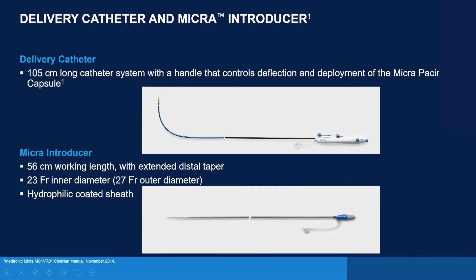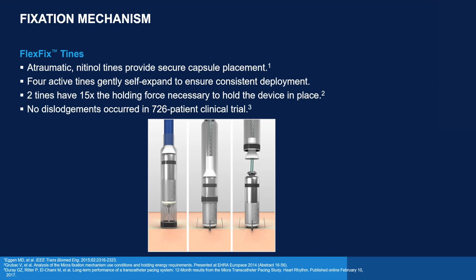So what happens when we unsheath the device is the tines open up. If you look here, the device is within the delivery catheter and the tines are folded up. As the delivery sheath is withdrawn, the tines open up and grip onto the trabeculation in the right ventricle. The apical section of the right ventricle is very trabeculated, with lots of crypts and crevices where these tines grip and basically hold the device in place. We also have the ability to test that it has actually gripped before we disconnect and fully deploy the device.